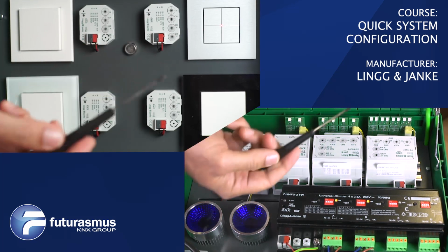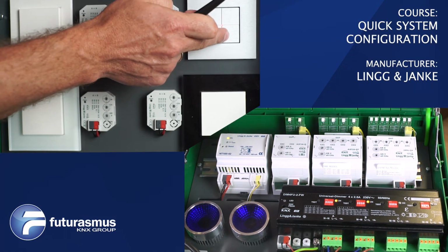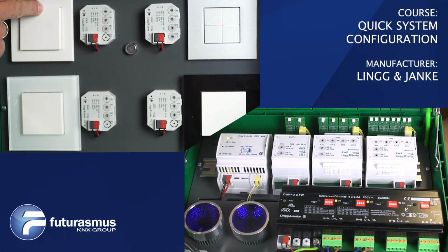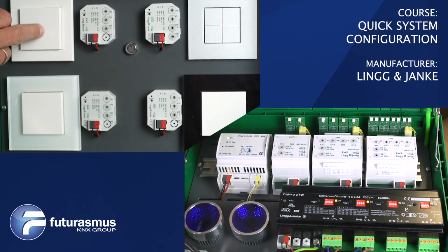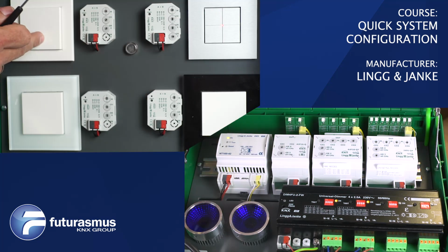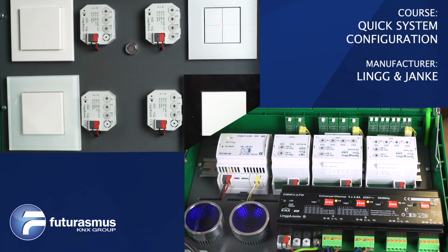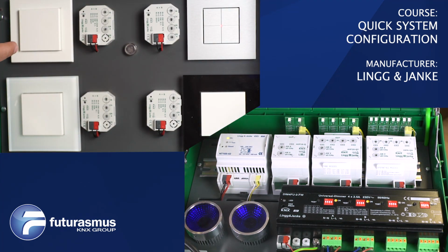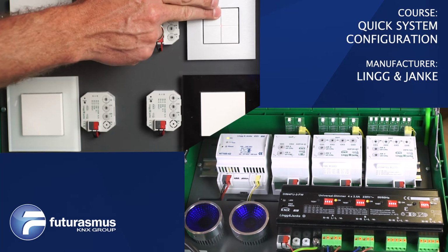So you just check, okay, it didn't work. Why it didn't work? Okay, it's because of this. So then you can switch on all, off all from here. And from here, you can switch on and off the first channel. Because now this one sends the group address to all the channels, and this one sends the group address just to this channel. So in this channel, both this one and this one is linked. This one is linked with the X, and this one is linked with the Y. Okay, so just to recap, this switches on and off this channel here, and this one is to switch on and off all the channels.